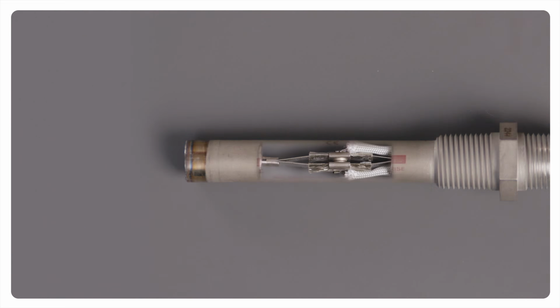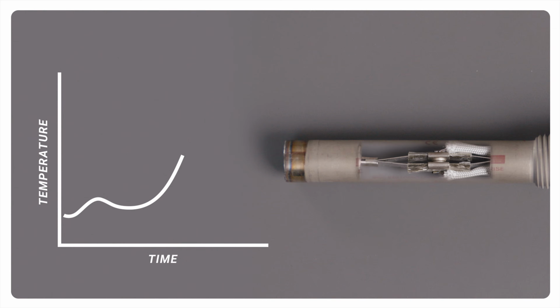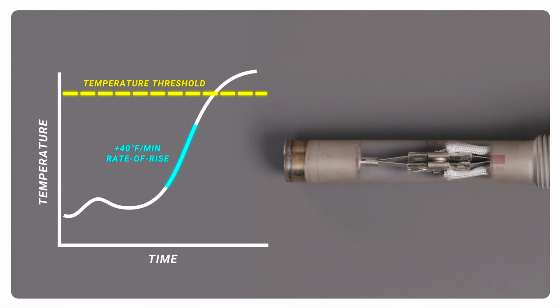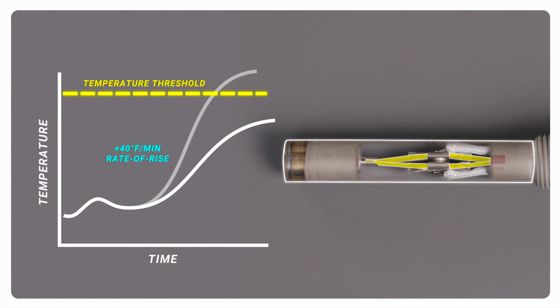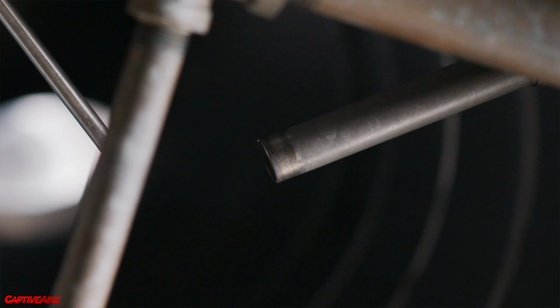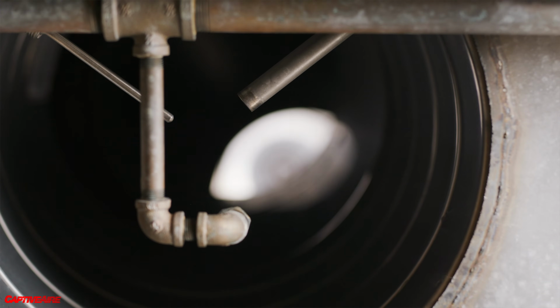The two mechanisms work together to only detect fires if the rate of rise is above 40 degrees per minute or if the absolute temperature has reached a set threshold. If the rate of rise is, say, 30 degrees per minute, the different metals will expand in a way that doesn't cause the sensor to be tripped. The main benefit of using this type of sensor is that we can quickly detect a fire, but we can also ignore flare-ups.